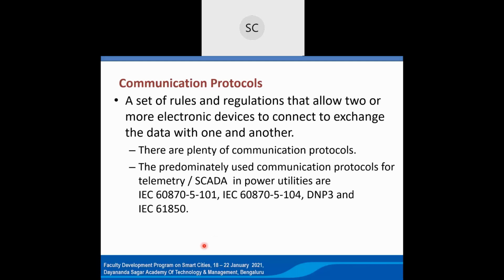For this, the IEC, International Electrotechnical Commission, has developed standards: IEC 60870-5-101, another one is 5-104, and DNP3. DNP3 is more popular in the US, and even in BESCOM they are using DNP3-built FRTUs, while in KPTCL we are using 104-built RTUs. And within the substations, the IEC 61850 communication protocol is used.